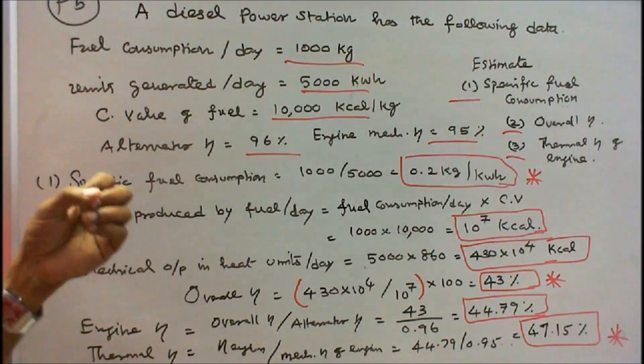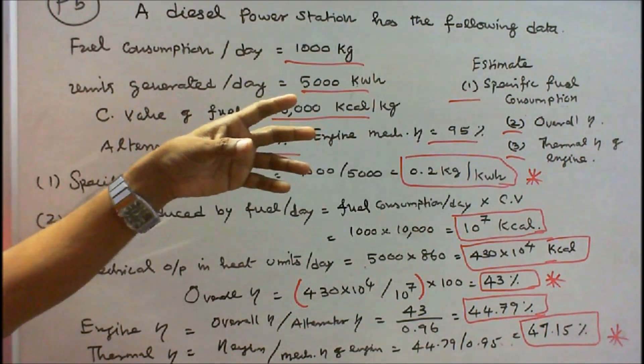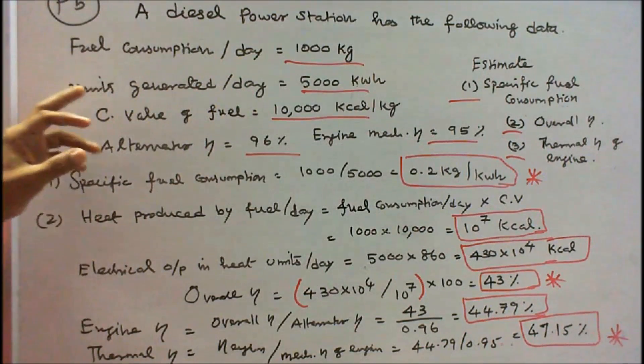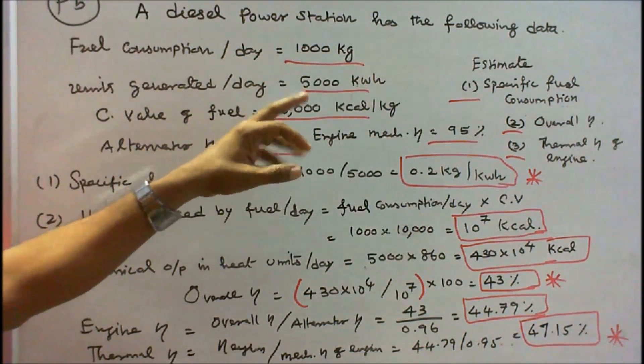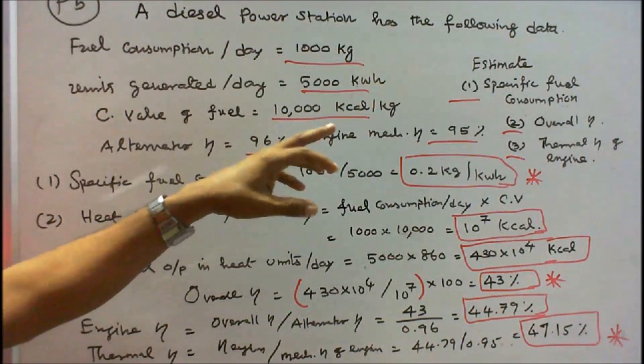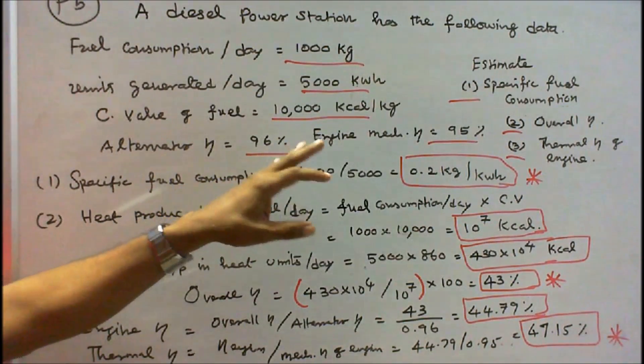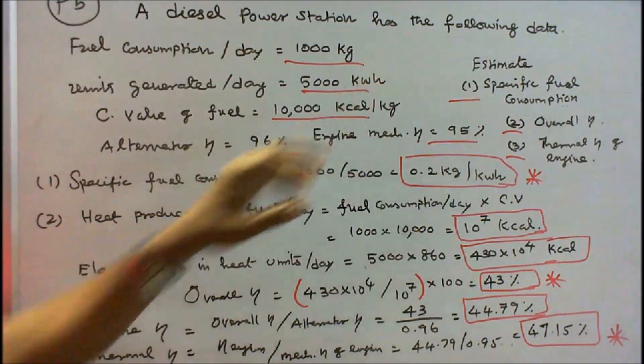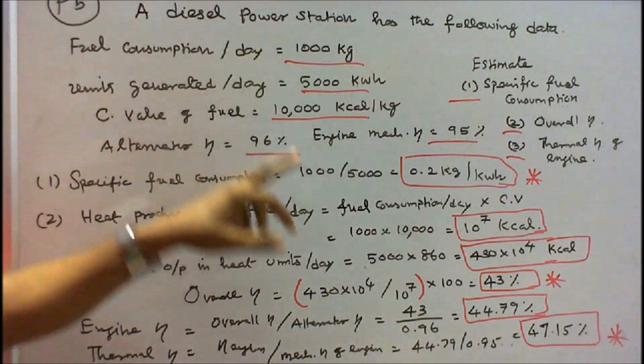Problem number 5: a diesel power station has the following data — fuel consumption per day = 1000 kg, units generated per day = 5000 kilowatt-hours, calorific value of fuel = 10,000 kilocalories per kg, alternator efficiency = 96%, engine mechanical efficiency = 95%. Estimate: (1) specific fuel consumption = fuel consumption per day ÷ units generated per day = 1000 ÷ 5000 = 0.2 kg per kilowatt-hour.